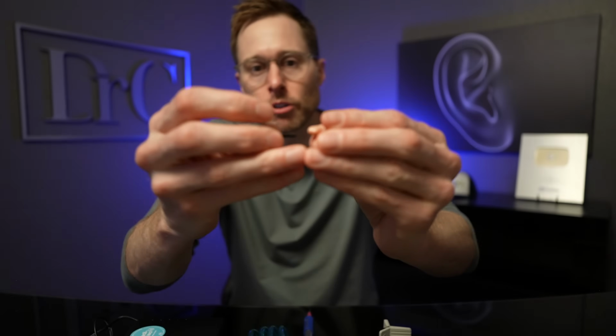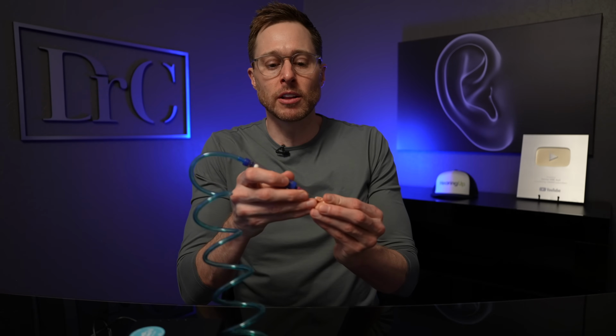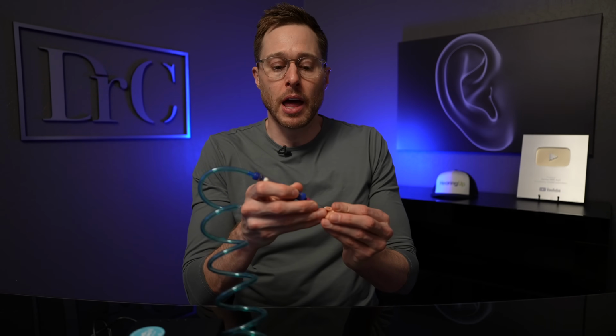Now, you can also use microsuction on these wax traps. Most people will actually take a wax filter and just go ahead and replace it anytime it gets dirty. So you guys have probably seen these little wax filters. I can go in and pull out the old wax filter, replace it with the new one, but some people produce so much earwax that they would literally have to do this a couple times a day. So instead, you can take your microsuction device and just very gently go into that wax trap and pull any wax out of it and prevent that wax from covering the little screens that are in there so it can emit sound back into your ear canal.